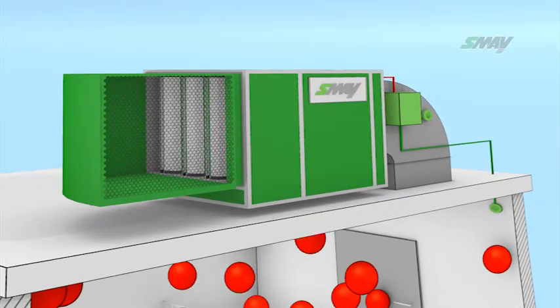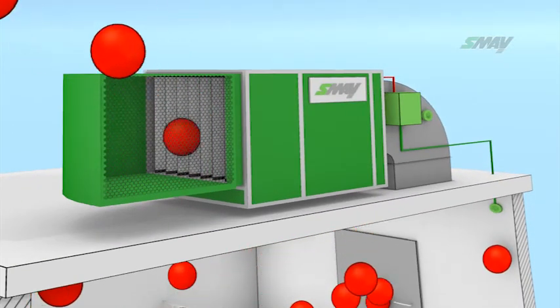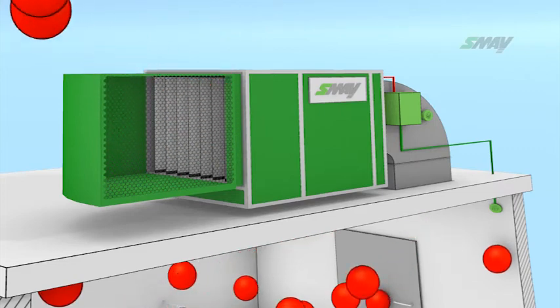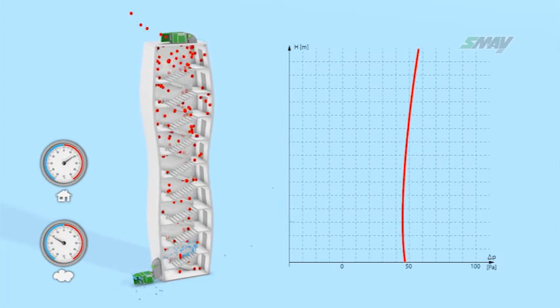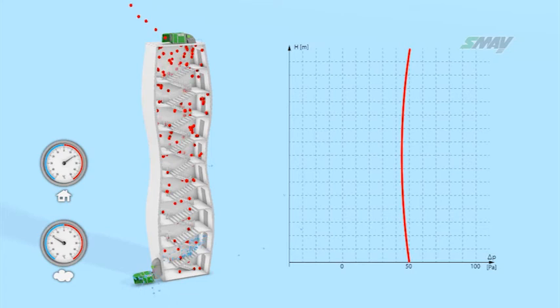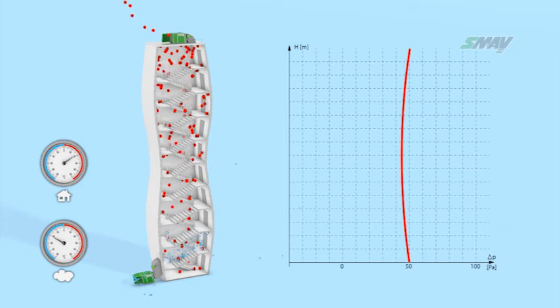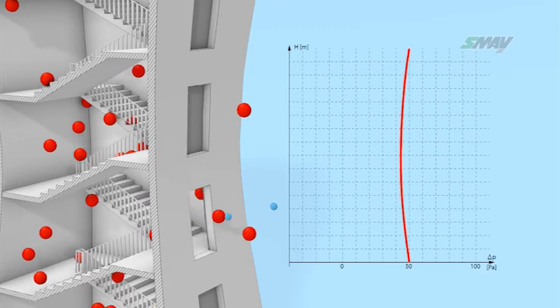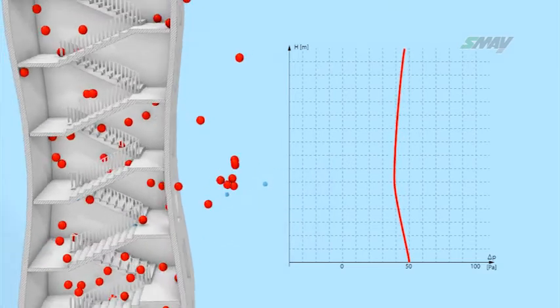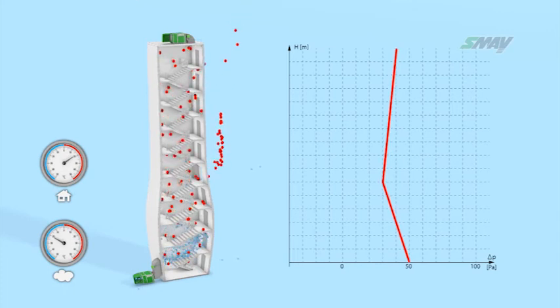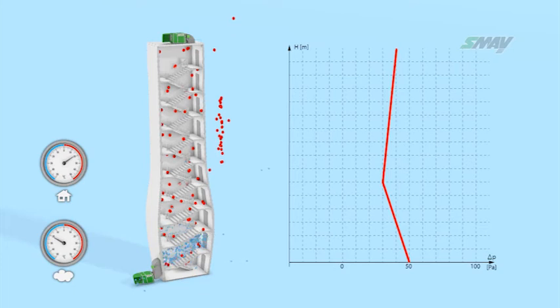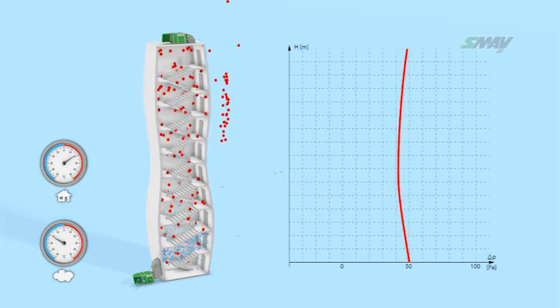The job of the fan is to maintain 50 pascal in the upper part of the stairwell. Due to the use of the Smay system, a stable distribution of static pressure across the entire stairwell under stack effect conditions is achieved through accurate control of air streams — supplied and extracted — and the accompanying airflow resistance. If doors are opened and pressure drops, then the fan will increase the stream of air supplied to the stairwell. Once the doors are shut, the system returns to observing the pressure criterion and supplies air needed to counteract the stack effect and flow resistance.